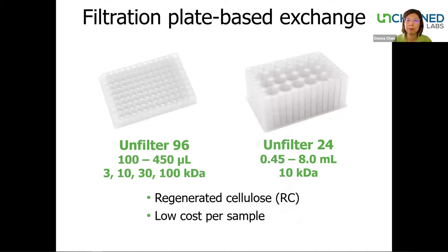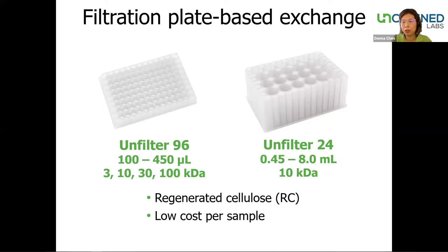Big Tuna is a filtration plate-based buffer exchange system. It uses two consumables: Unfiltered 96 and Unfiltered 24. Both are made with regenerated cellulose membrane and are in SBS standard format, so they're compatible with automation instruments. Unfiltered 96 is a 96-well plate with a volume input of 100 to 450 microliters and four molecular weight cutoff options ranging from 3 kDa to 100 kDa. The Unfiltered 24 is a 24-well format plate with sample input volume from 0.45 to 8.0 milliliters, with a 10 kDa cutoff option.